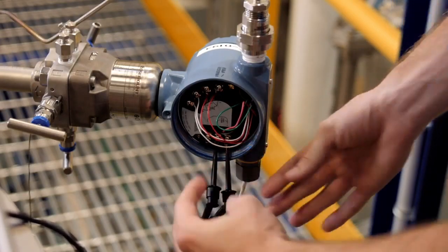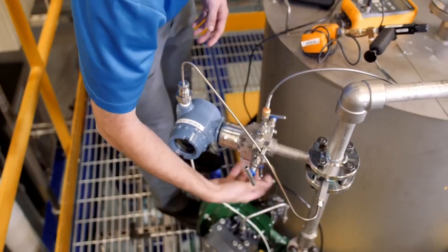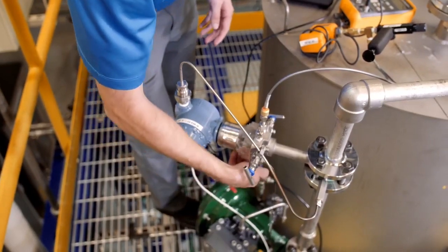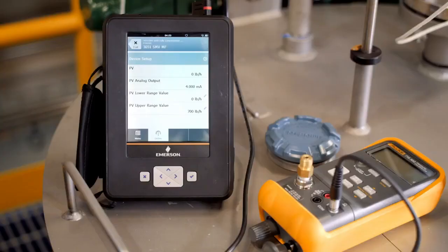The first calibration point will be a zero trim. A zero trim is a zero-based offset that provides a baseline for the measurement. For this reason, the equalizing valve must be manipulated so that the high and low sides of the transmitter are experiencing equal pressure, or zero DP.